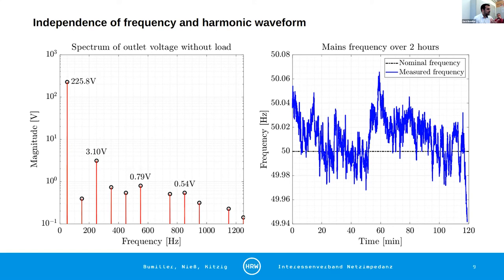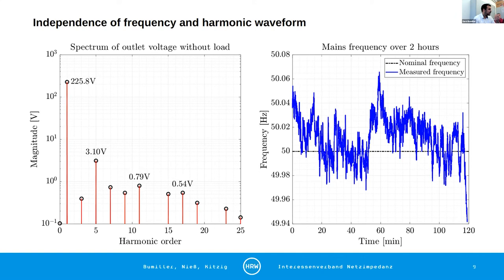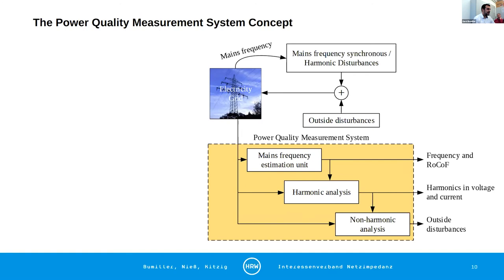It's important now for us, if we talk about harmonics and harmonic composition of signals, they will stay constant in waveform for different mains frequency values. So we do now talk about the harmonic order, as you all know. This is important because our power quality measurement system concept is modeled to estimate that the grid voltage that we measure is a superposition of mains frequency synchronous or harmonic disturbances, which are, for example, caused by non-linear loads, and we have outside disturbances. This could, for example, be switching power supply switching frequencies or inverter switching frequencies.